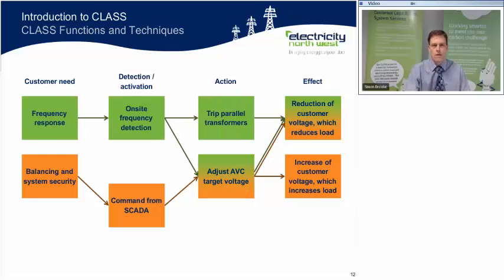The second function is a frequency response function. This is a function where the detection occurs on site because we require a fast-acting function. One of the actions is that we will adjust the target voltage, but we may also trip one of a pair of parallel transformers, and I'll describe that in more detail later, with the effect being that we can reduce the voltage and so reduce demand.